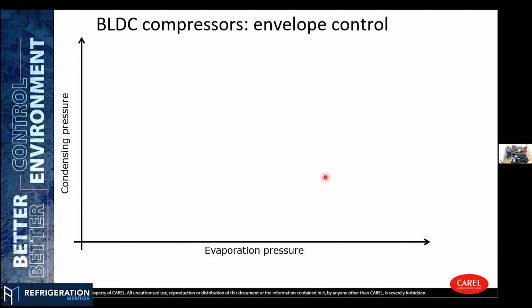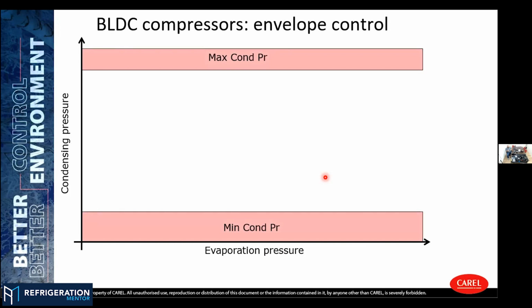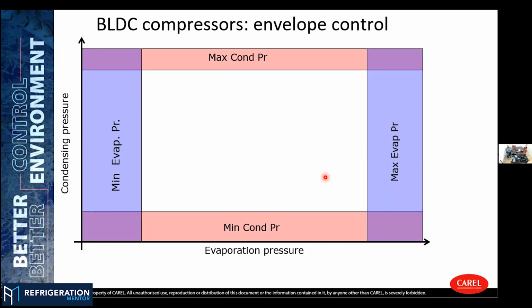So basically, here we have a graph with evaporation pressure and condensing pressure, and the correlation that will make the zones of operation. As you may know, all compressors have a minimum condensing pressure and a maximum condensing pressure rated by the OEM, the manufacturer. So these are the limits in terms of condensing pressure. Also, for the evaporation side, there are the same: minimum evaporation pressure and maximum evaporation pressure. So we start to draw where the compressor should work. Mainly, we should work inside the middle, not below the minimum evaporation pressure, not above the maximum. And for the condensing, the same.